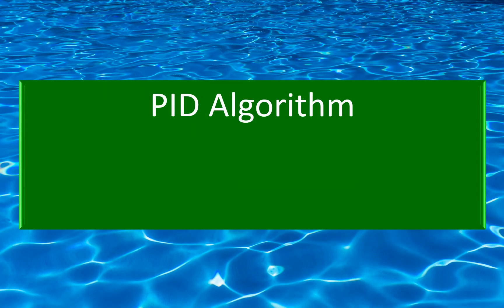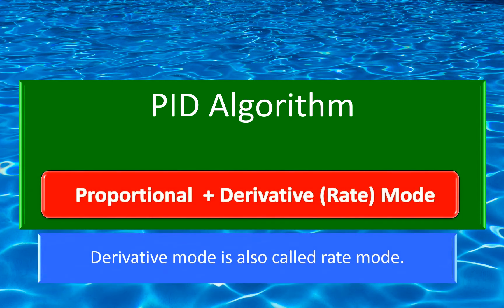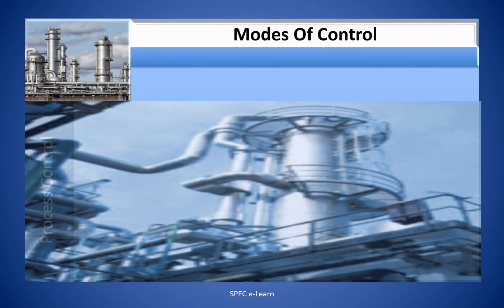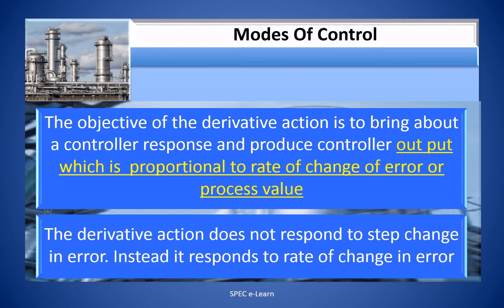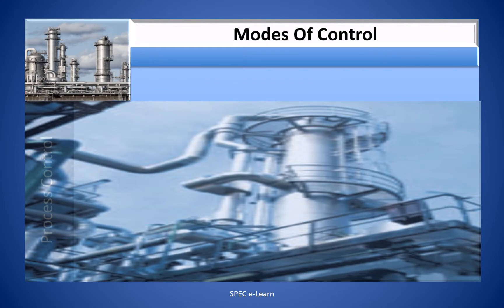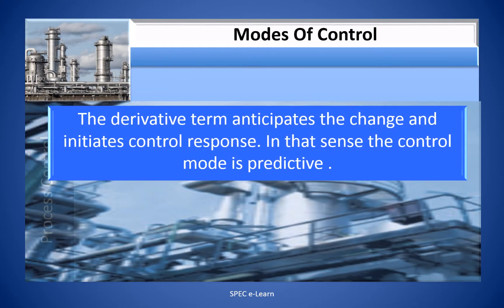Proportional plus Derivative Mode — Derivative is also called Rate Mode. The objective of the derivative action is to bring about a controller response and produce the controller output which is proportional to the rate of change of error or process value. The derivative action does not respond to a step change in error; instead, it responds to the rate of change in error. The derivative term anticipates the change and initiates control response — in that sense, the control mode is predictive.